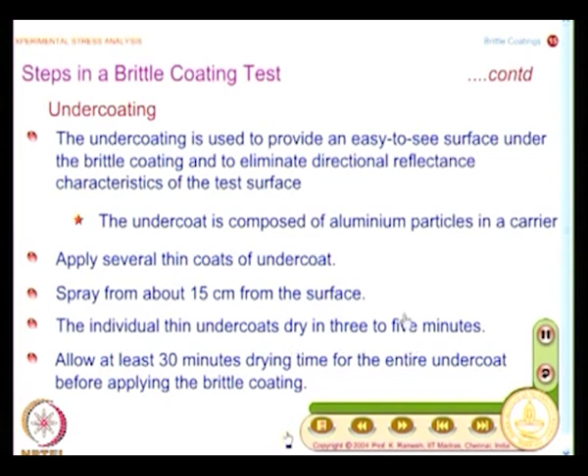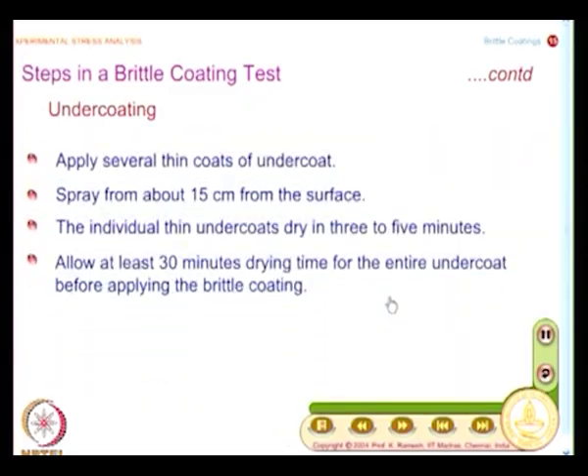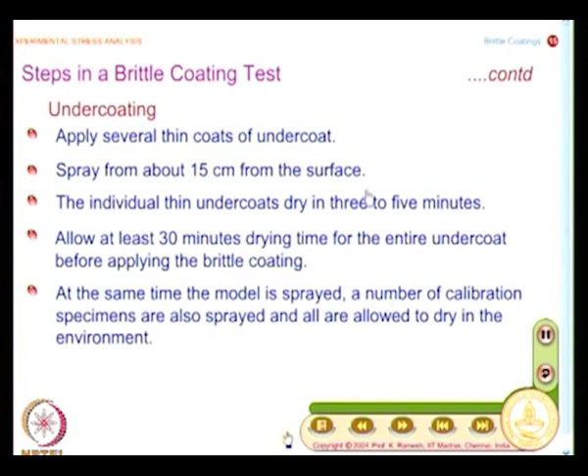So, you have a recommendation what kind of a cycle that you need to follow, and after you have made several thin coats of undercoat, allow at least 30 minutes drying time for the entire undercoat before applying the brittle coating. What you will have to keep in mind is, though these procedures look very detailed, this has come about by several iterations operated by the manufacturer, and it is better that you follow these recommendations.